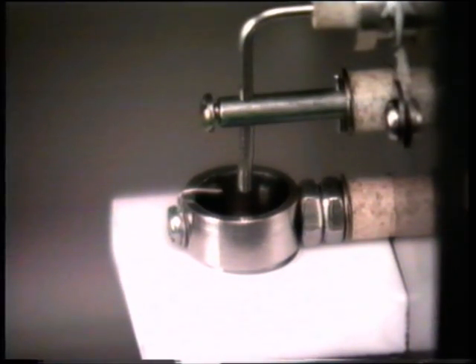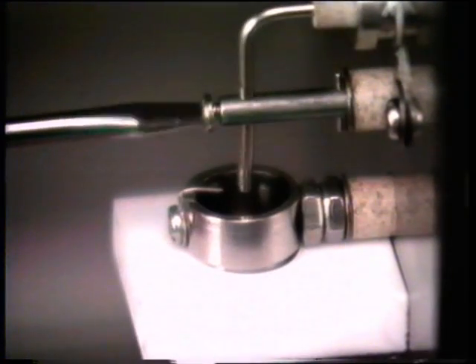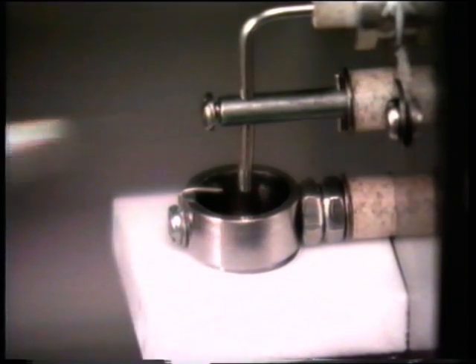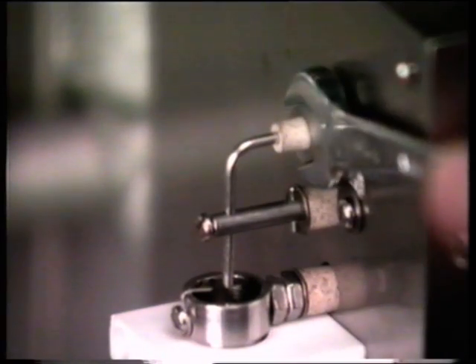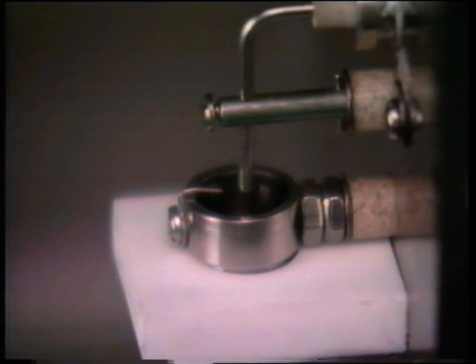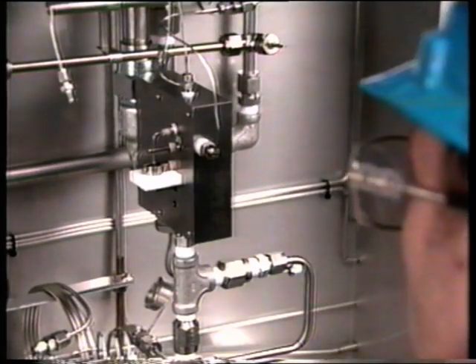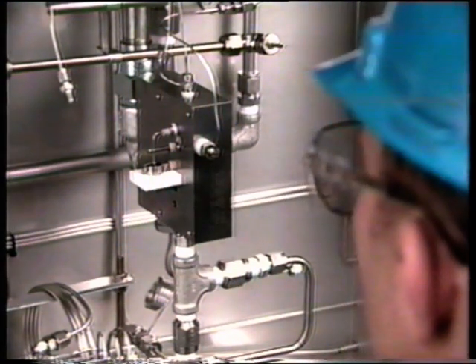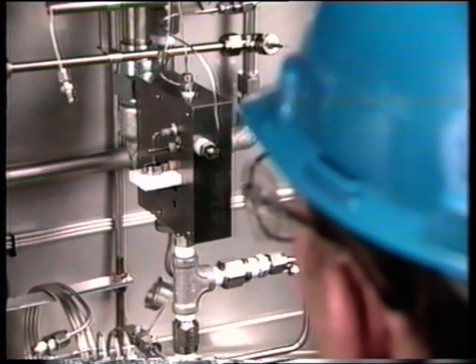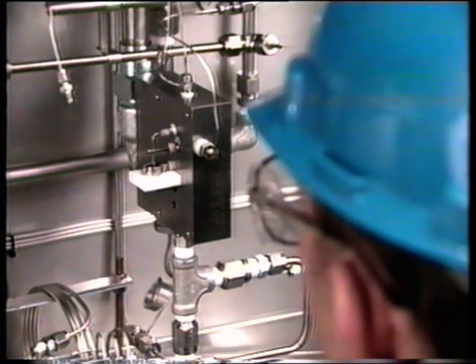Verify that the burner tip is still centered over the collector and about 1/32 of an inch above it. Tighten the screw in the end of the bias ignite electrode and tighten the burner clamp nut. Be certain that the end of the igniter wire is near the level of the burner tip and about 1/16 of an inch from it. Verify the alignment of the thermocouple, the collector, the burner tip, and the igniter wire. If alignment is incorrect, loosen nuts and screws, realign, and finger tighten the connections.